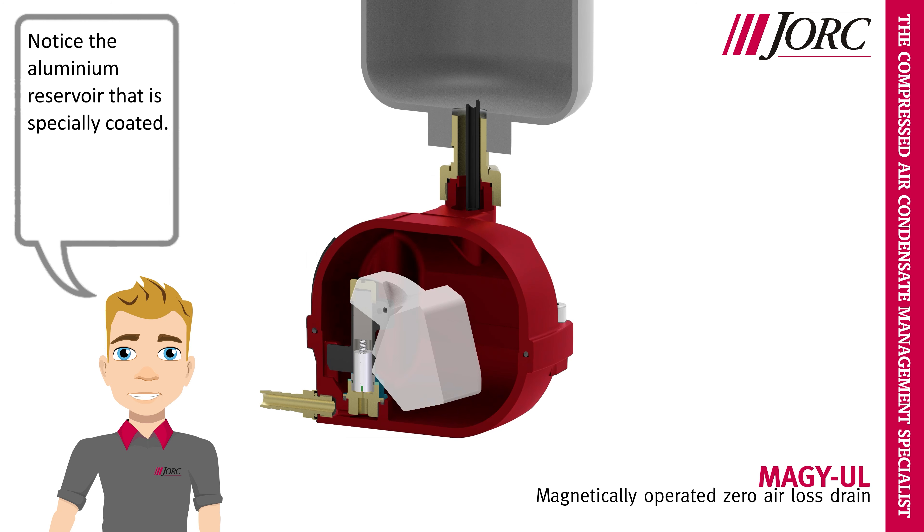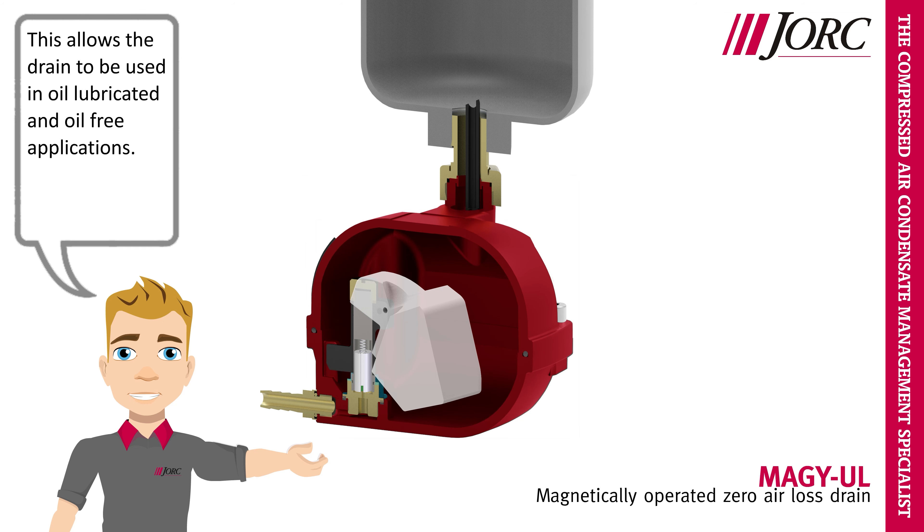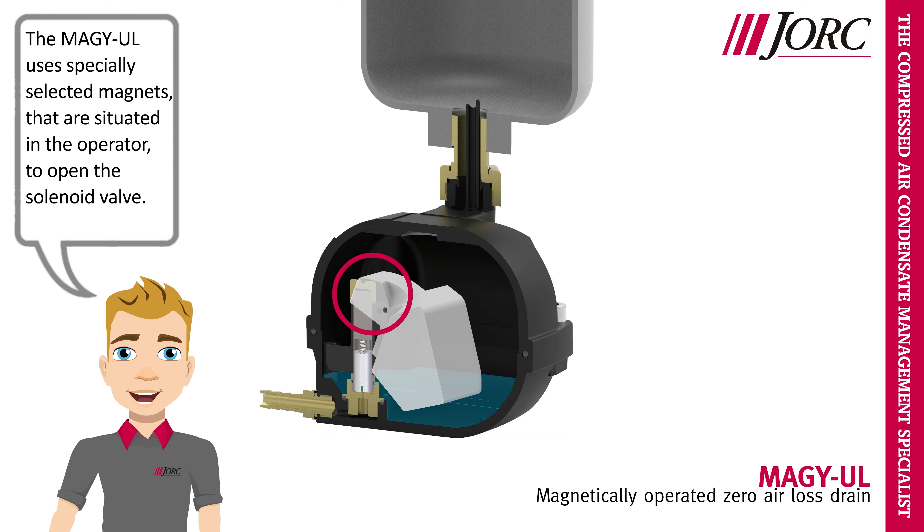Notice the aluminium reservoir that is specially coated. This allows the drain to be used in oil-lubricated and oil-free applications. The MAGY-UL uses specially selected magnets that are situated in the operator to open the solenoid valve.